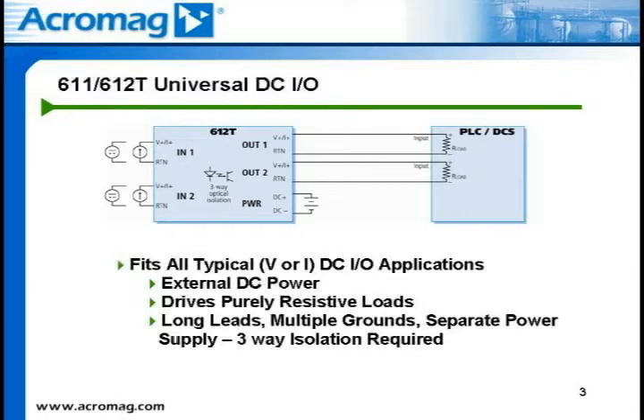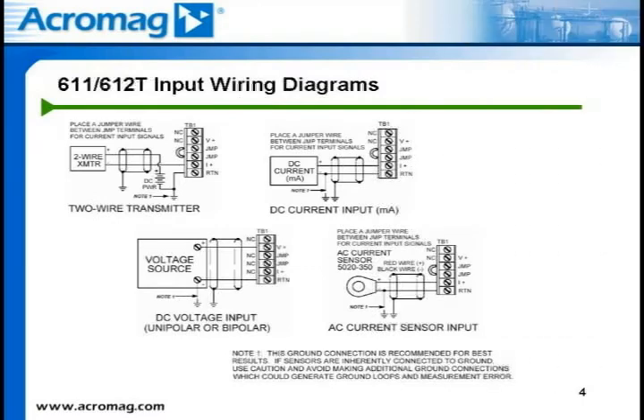With a low input burden of 10 ohms and the ability to drive up to 550 ohms, the 611 or 612T isolated transmitter is perfect for boosting the signal in these situations. Here we show input electrical hookups based on common DC current and voltage applications. First, we have a two-wire transmitter field device. It involves the use of a DC power supply to power both the field transmitter and the input loop.